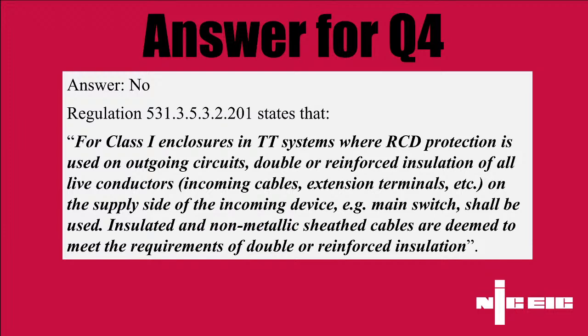So because you've got that insulation method at that part of the installation, that will omit the need for having the RCD there. But obviously, if that wasn't there, then yeah, you might be looking at RCD upfront protection. Yeah, absolutely. And so it's all about the fact that if we can rely on that double insulation, it needs to be maintained until the tails are inside the enclosure.